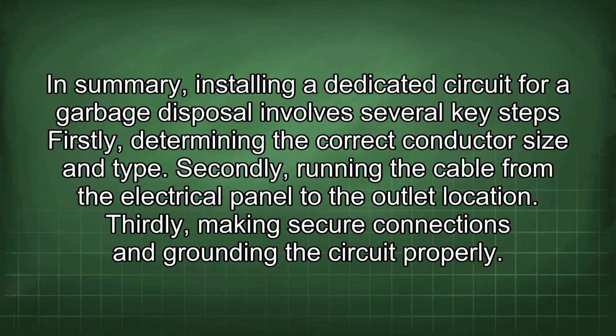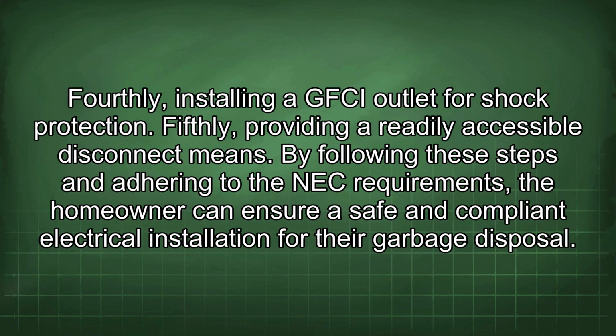In summary, installing a dedicated circuit for a garbage disposal involves several key steps. Firstly, determining the correct conductor size and type. Secondly, running the cable from the electrical panel to the outlet location. Thirdly, making secure connections and grounding the circuit properly. Fourthly, installing a GFCI outlet for shock protection. Fifthly, providing a readily accessible disconnect means.